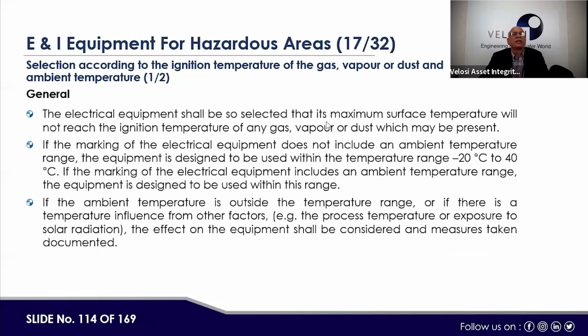Next, selection according to the ignition temperature of the gas. For example, whatever gas is available there, the surface temperature of the equipment should remain below that, right? Similarly, the electrical equipment shall be so selected that the maximum surface temperature will not reach the ignition temperature of any gas present in that area, the T3, T4, T5. Similarly, if the marking of the electrical equipment does not include any ambient temperature range, the equipment is designed to be used within the temperature range of -20 to 40 degrees Celsius.